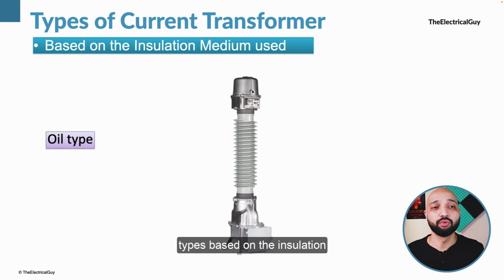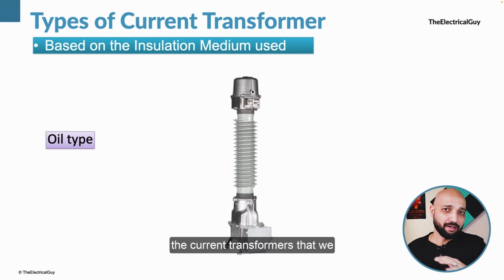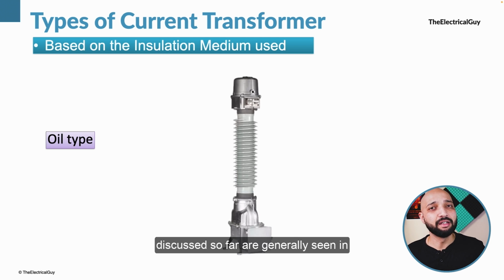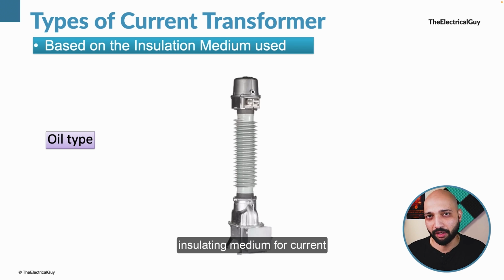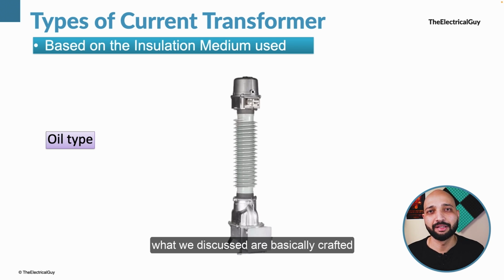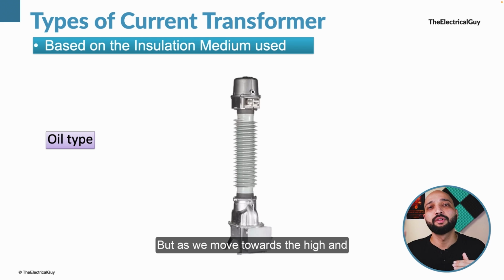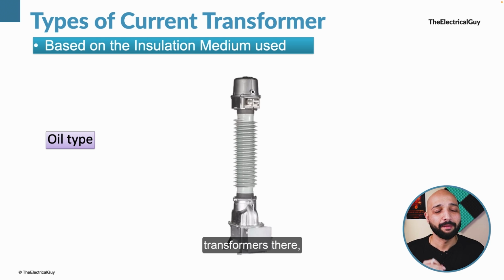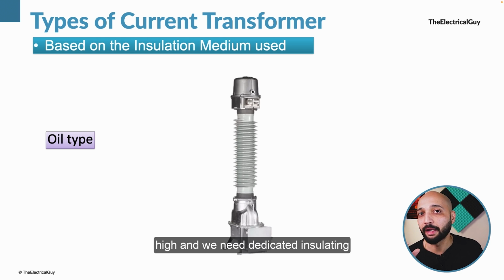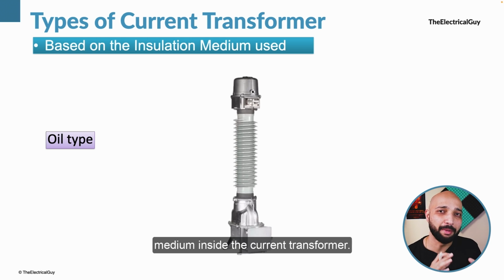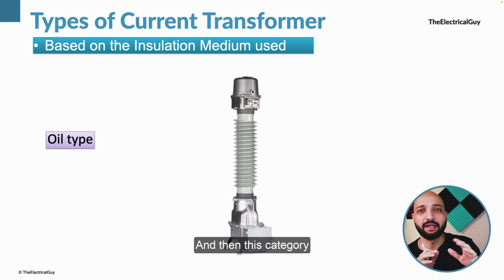Now moving on, let us talk about the types based on the insulation medium used. Now the current transformers that we discussed so far are generally seen in low and medium voltage switchgear, wherein the voltage rating is quite low and you don't have to have a dedicated insulating medium for current transformers. So all these current transformers we discussed are basically crafted in epoxy resin, and you don't need to have a dedicated insulation for that. But as we move towards the high and extra high voltage current transformers, there the voltage rating is of course very high, and we need a dedicated insulating medium inside the current transformer. And then this category comes into picture.